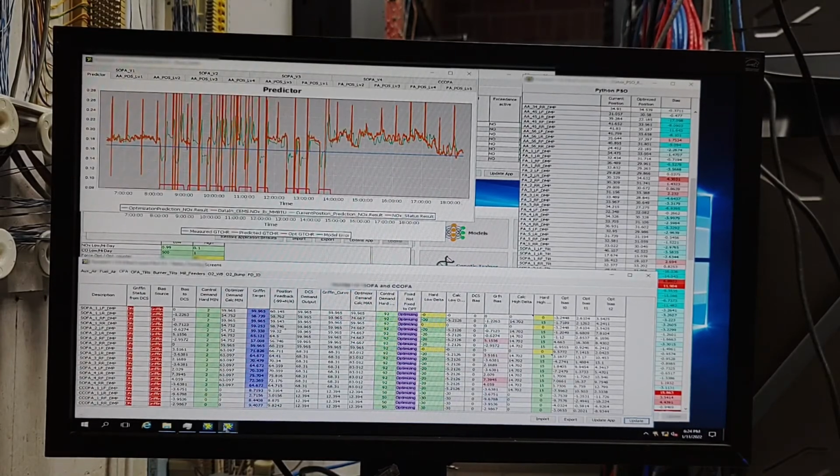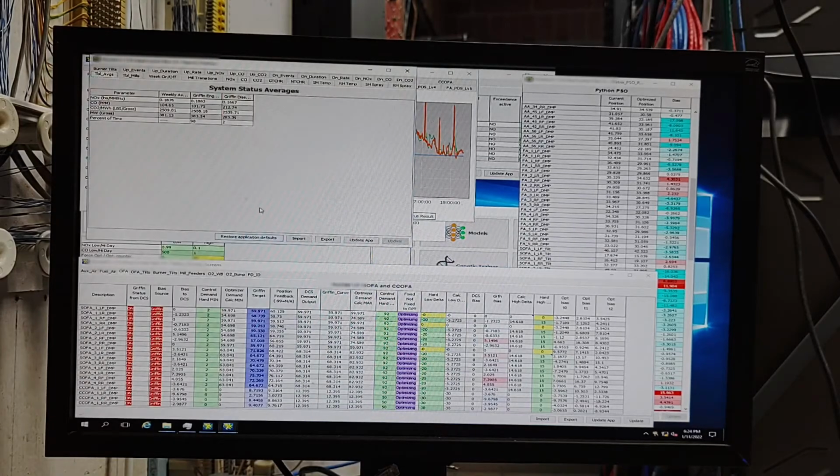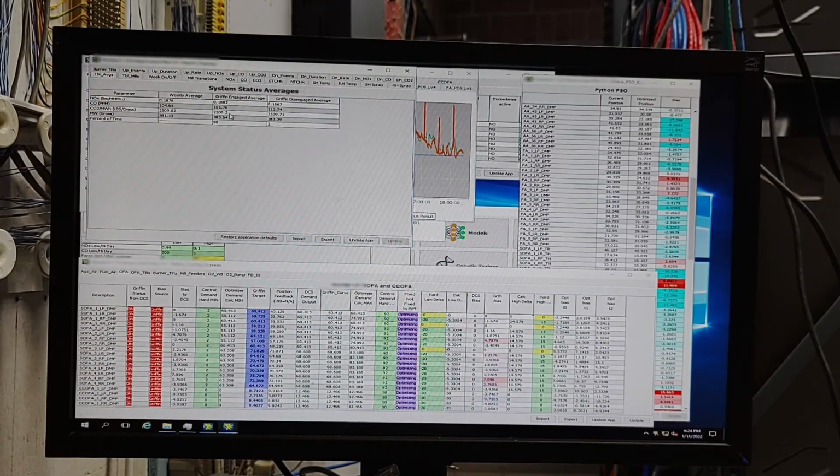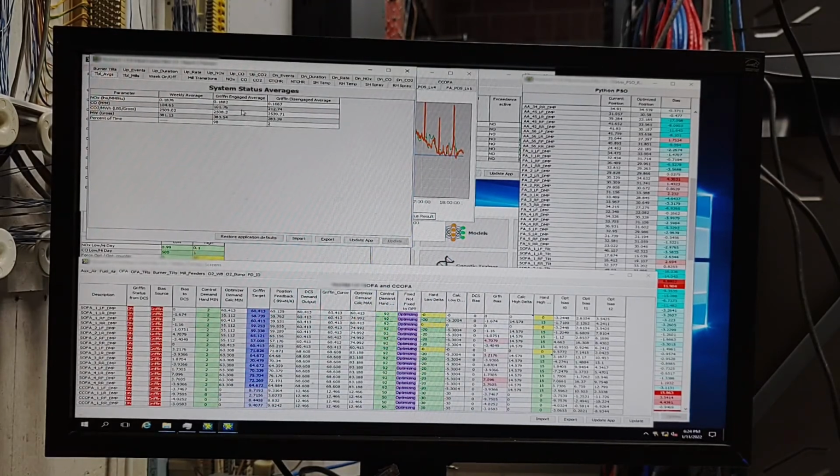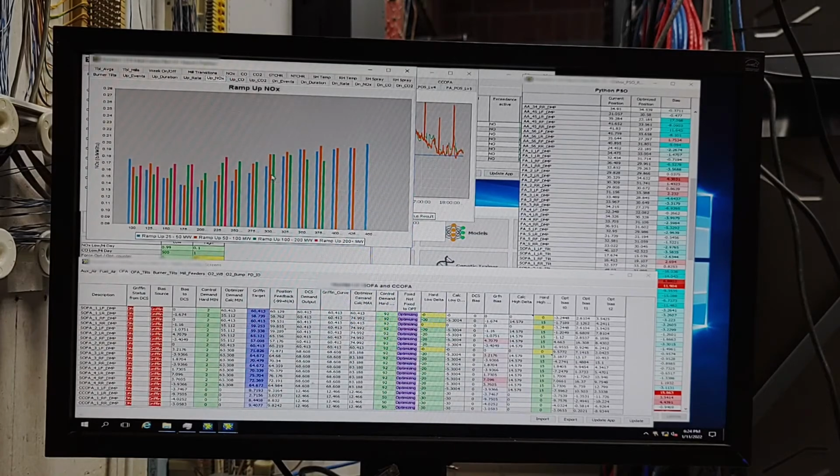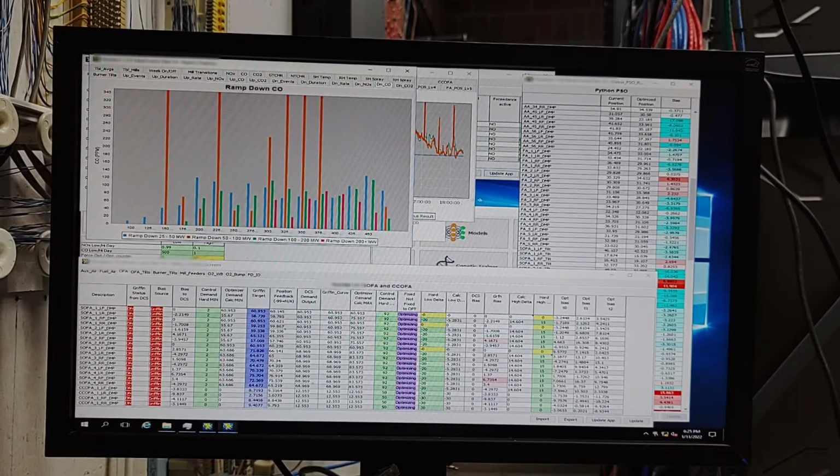I believe that's probably everything that I'd like to show. Maybe one last thing is just the ability to do calculations in real time and comparisons and analysis. This table here shows how the unit's been performing with the Griffin system engaged and disengaged. See another metric of efficiency, the CO2 emitted per megawatt hour, about a 1.3% improvement with Griffin engaged. And you also see a high service factor of the Griffin system. We can do analysis of how emissions perform during certain ramping situations, up or down, or break those out in any way that is of interest to the unit.